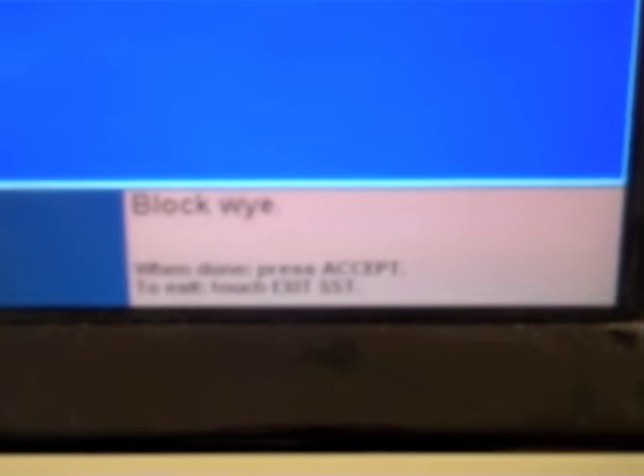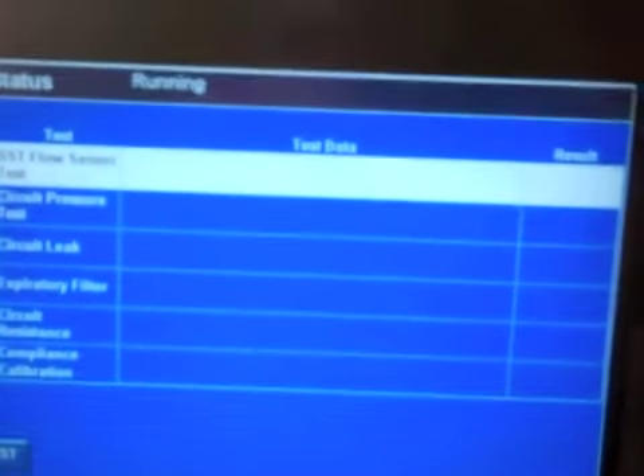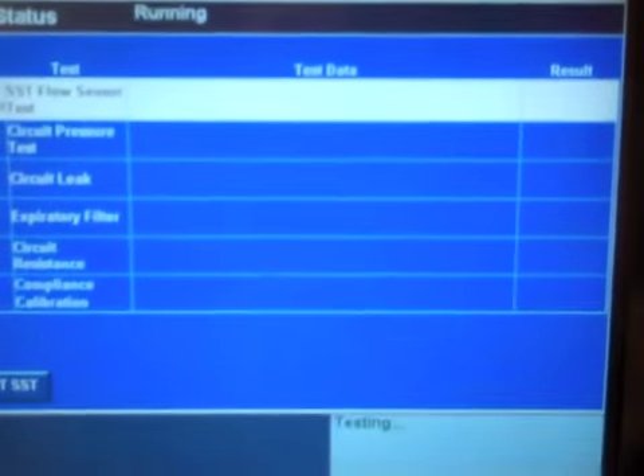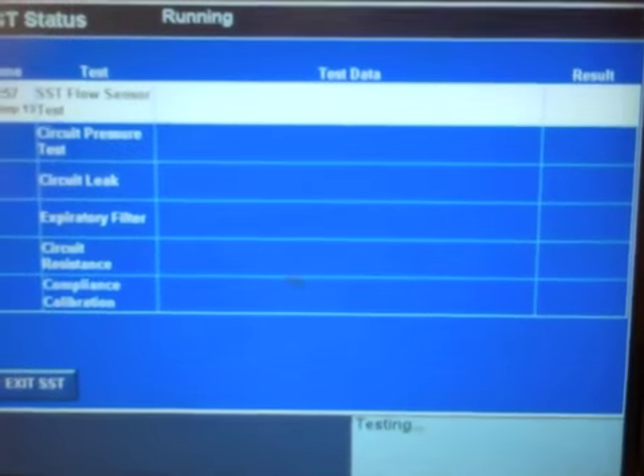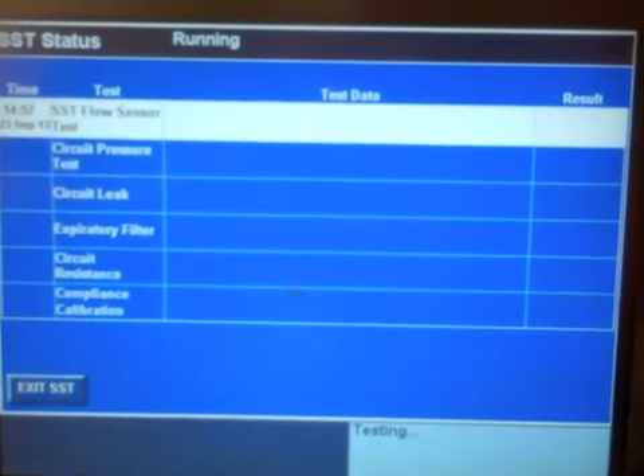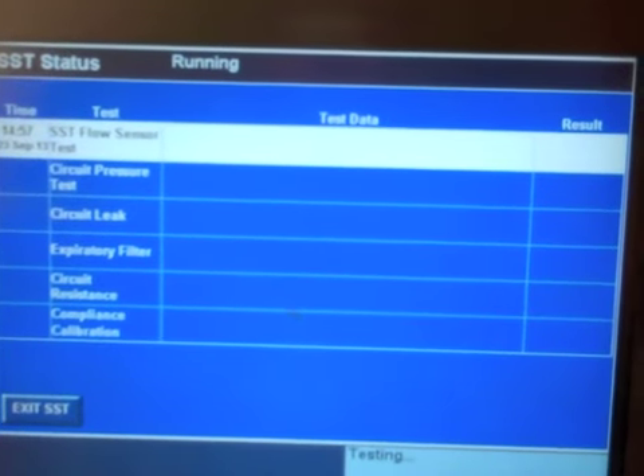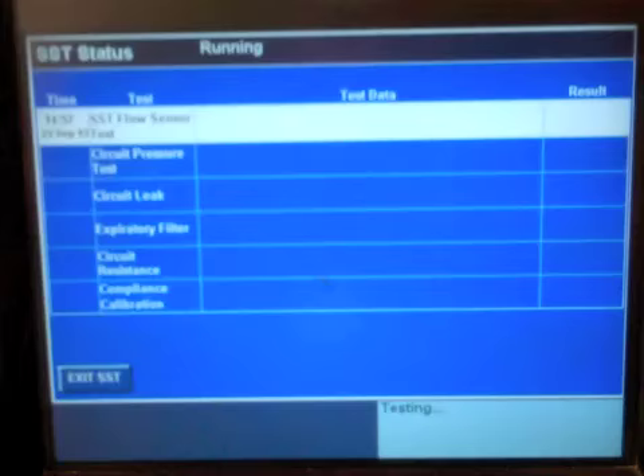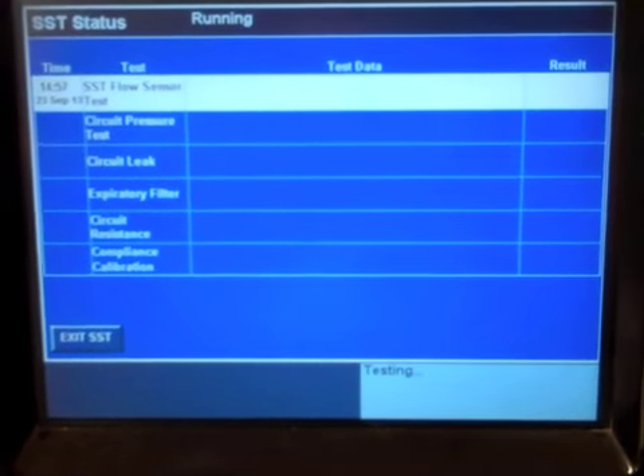I'm going to go ahead and select accept. It's now telling me to block the Y. Okay, I'm just going to pop a cap into my circuit here. I'm going to hit accept, and it's going to start to pressurize the circuit and measure the flow. So this might be a relatively boring video, but I want to keep it going through the entire test so you see what prompts come up and what the steps are.